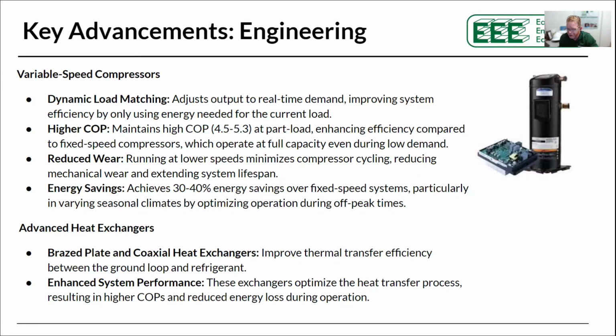The big advantage is dynamic load matching: it allows the unit to run at and match the load the building needs. We're not running a compressor at 70% or 100% capacity if we only need 15%. That has a huge impact on the overall COP of the system, and that's how you get really high COPs at part load.